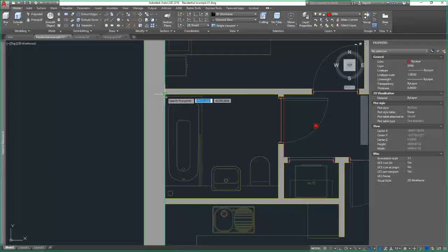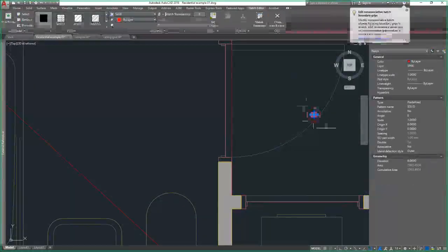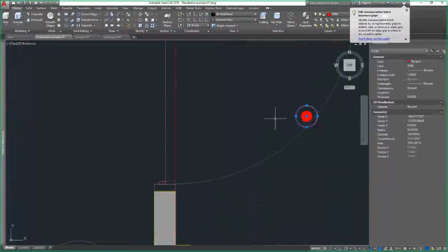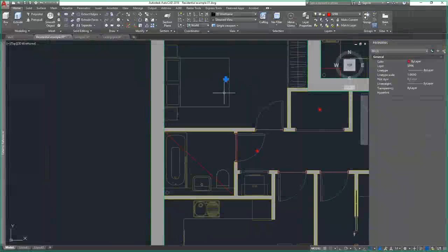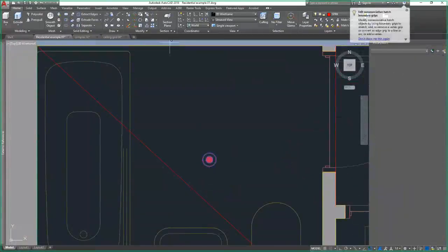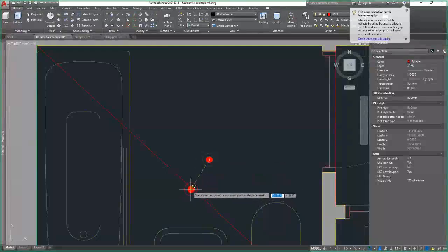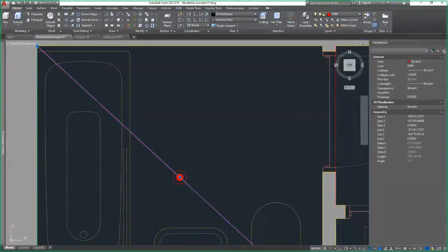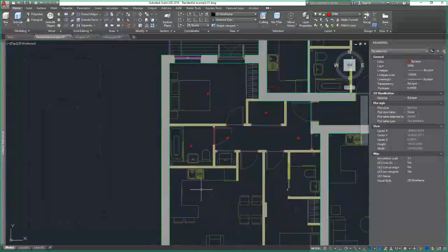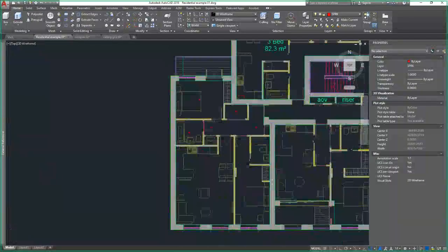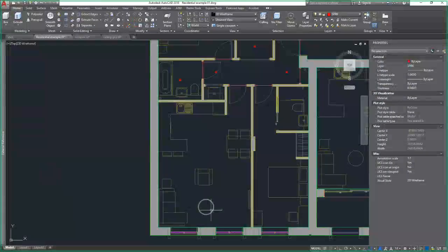Again, there's certainly no harm in sprinkler protecting it. So you could add a note to the drawing saying, I haven't sprinkler protected this bathroom because it is smaller than 5 square meters. Or you could put a sprinkler head in it, and make a comment to say this head is not strictly required, and wait for further instruction on whether the main contractor or whoever's in charge is going to want to keep that head or not. It's not going to add much cost at all because we've already got the pipes in there. A head's a few pounds, so it's not going to be a big deal.